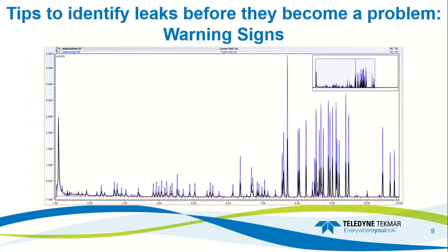Here's an example of the leaking vial cap in soil mode. A loose cap is shown in black and the tight vial cap is shown in blue. You lose a lot of response when your system isn't leak-tight.